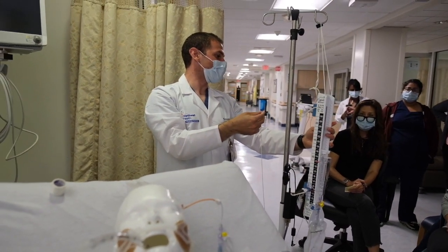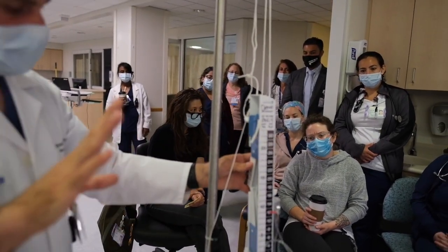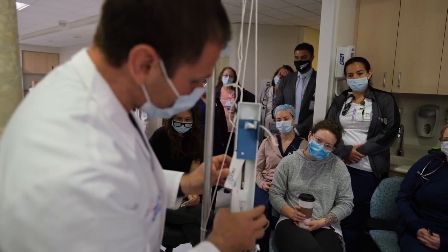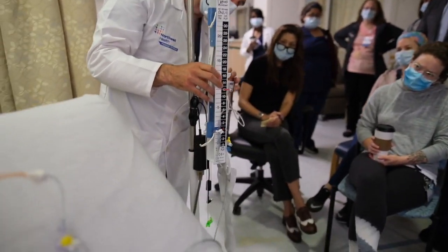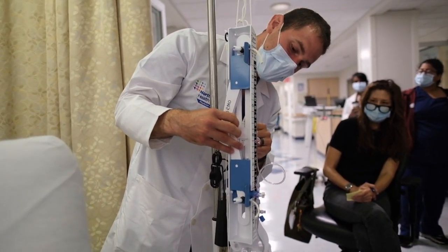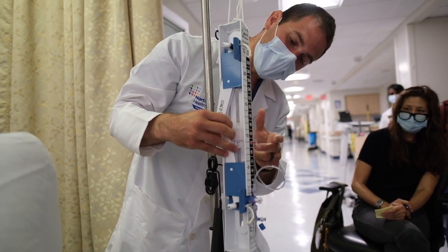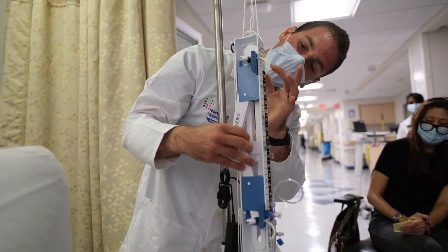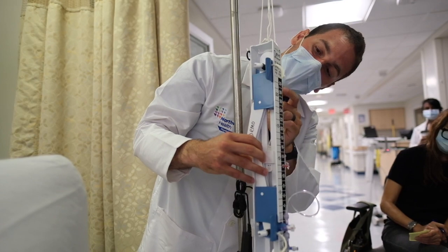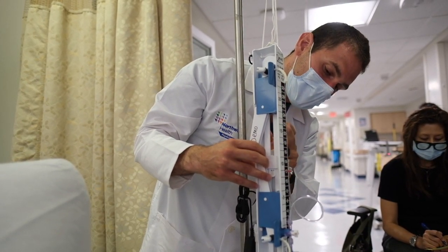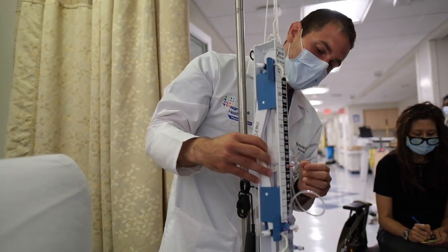They made a little fancy hook on the back too, so you can always take the ring here and put it on there. Okay, so now we've got it level. The tubing's going to come up into the collection chamber here. Before we get to the collection chamber, you'll see a red line right here and a bunch of numbers. One side is millimeters of mercury, and the other side is centimeters of water. We want to focus on centimeters of water, which is the black portion of the meter here.